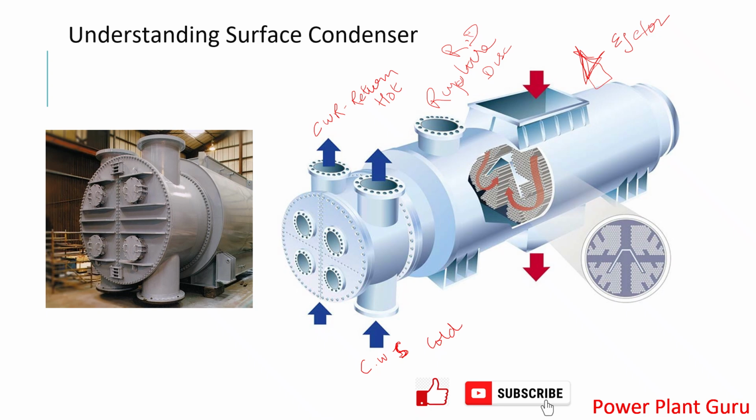So why is RD required? We know that the steam condenser is designed to operate at a low pressure, or rather a negative pressure. So all these joints and everything are designed in such a way that there is no ingress of air. That is how the equipment is designed for low pressure, not high pressure. The rupture disk is given for protection if, in any case, the pressure inside this vessel goes high, then there will be a rupture disk.